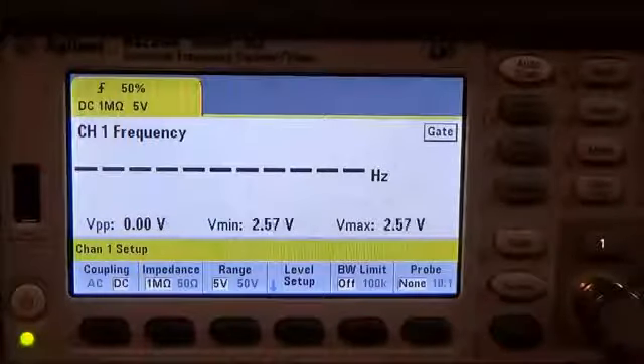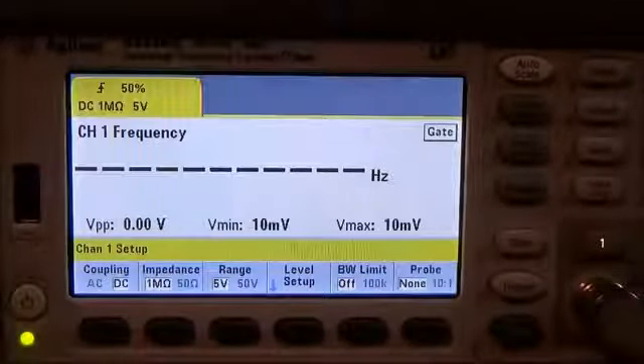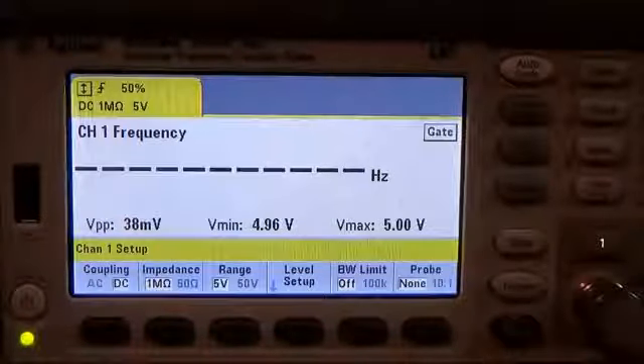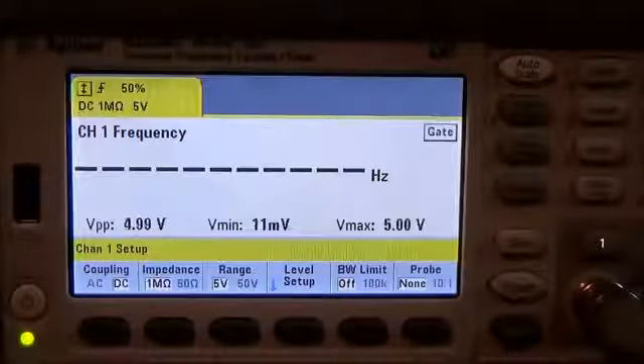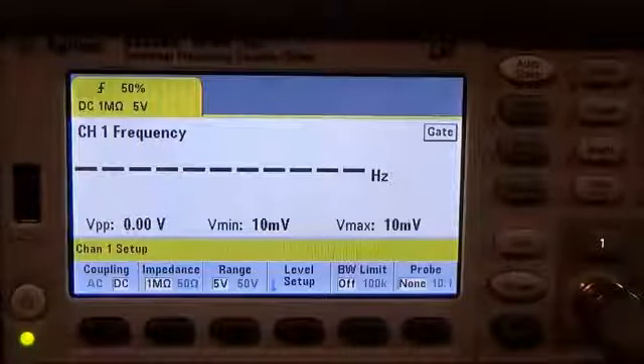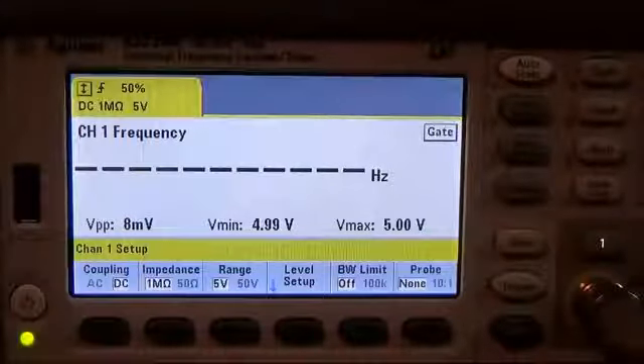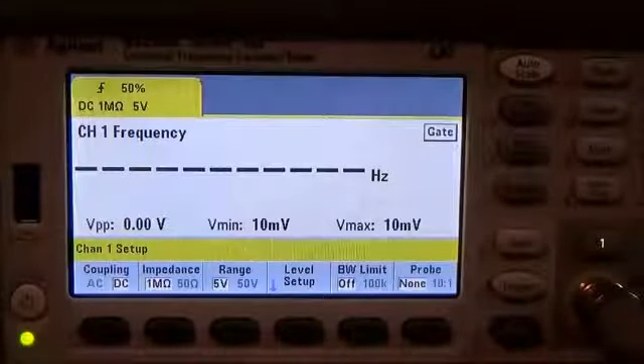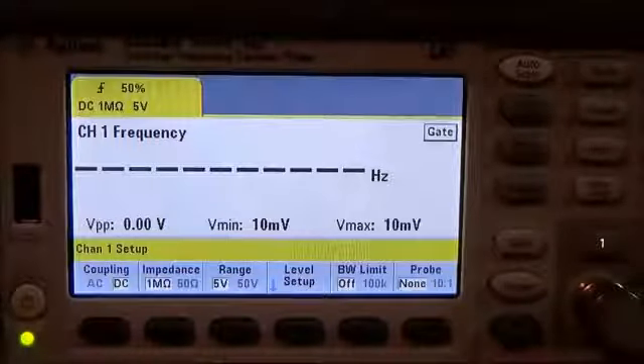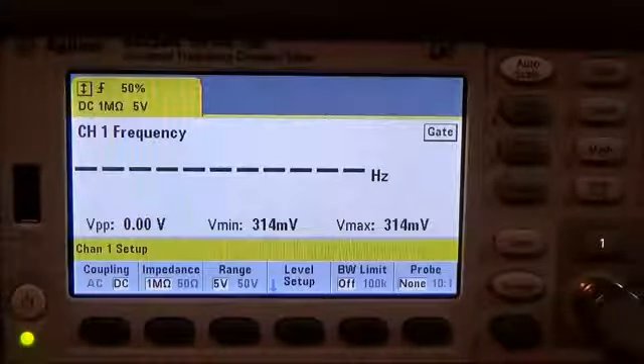The counter is specified for DC coupling down to a millihertz and for AC coupling it's only down to 10 hertz. So for our low frequency signal here of 1 hertz we would want to be on DC coupling.